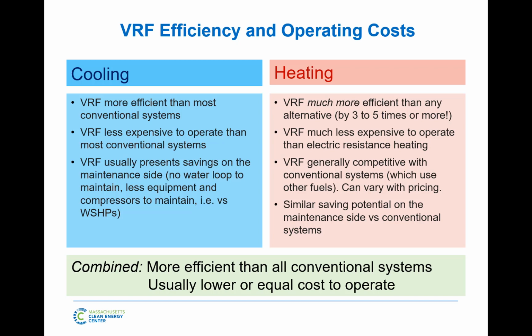So I was just comparing a VRF system, which is an air source heat pump. Oh, yeah, good point. I think the question was about what I'm comparing VRF to with water source heat pumps. So in this section, for cooling, or in both, I'm comparing VRF, which is air source heat pumps, with potential conventional systems that you might be comparing it with. I'm looking a bit at multi-residential commercial buildings. So I'm using water source heat pump, chiller fan coil systems, those types of central systems. But VAV can also be used in these comparisons.